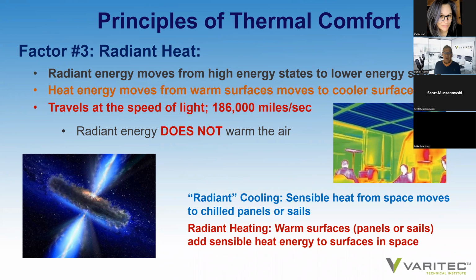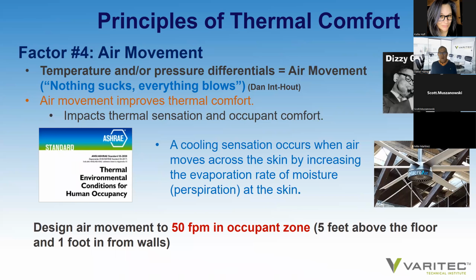It warms surfaces. So radiant cooling is sensible heat transfer from a space that moves from either a chilled panel or sail mounted in the ceilings, possibly the walls, that absorbs the heat energy of surfaces within that space, such as a human occupant with a bodily temperature, hopefully of 98 degrees. It can also be a heating source by heating a surface within a space and emitting that radiant energy to surfaces, such as occupants in the space, creating a heating effect. Air movement is another factor. Having proper air movement in a space will impact thermal comfort. Wherever there's a temperature or air pressure differential, you will have air movement. Air movement improves thermal comfort because it allows our bodily perspiration to more efficiently evaporate, giving a cooling effect.